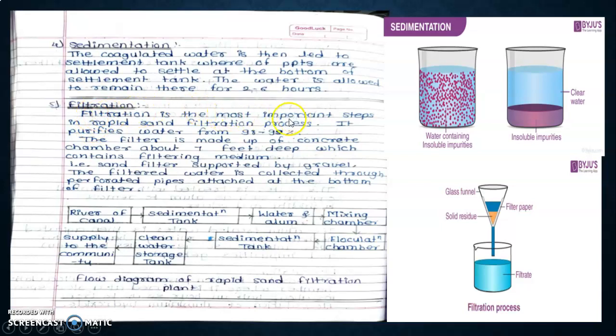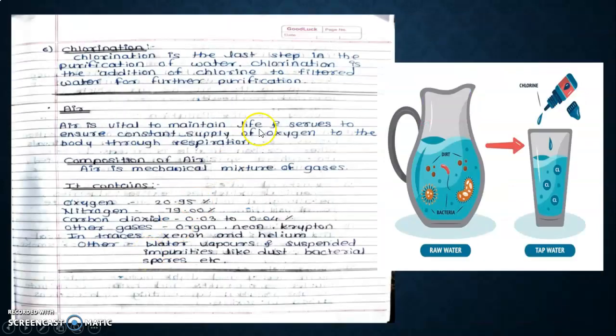Filtration is the most important step in rapid sand filtration process. It purifies 98 to 99% of water. The filter is made up of concrete chamber about 7 feet deep which contains filtration medium, that is sand filter supported by gravels. The filtered water is collected through perforated pipes attached at the bottom of the filter.